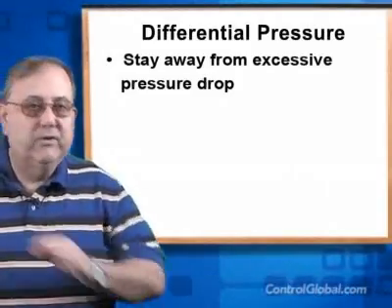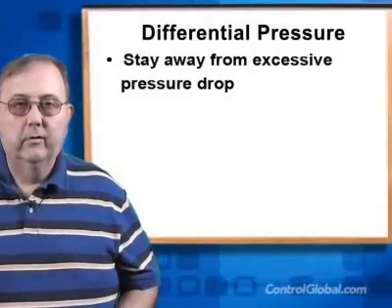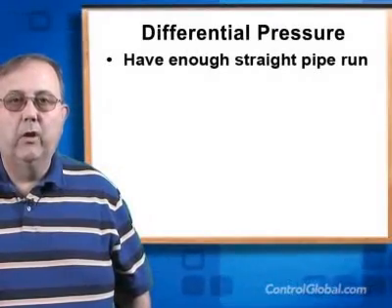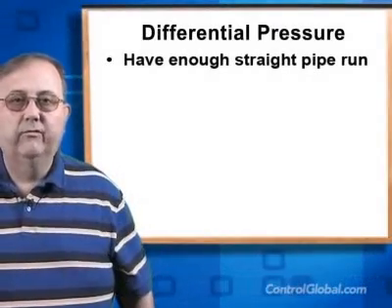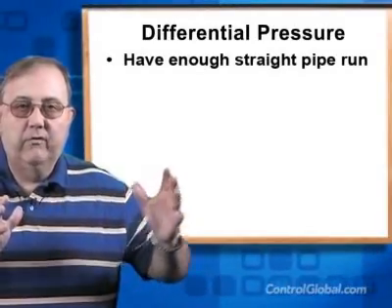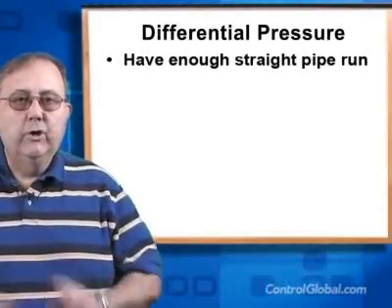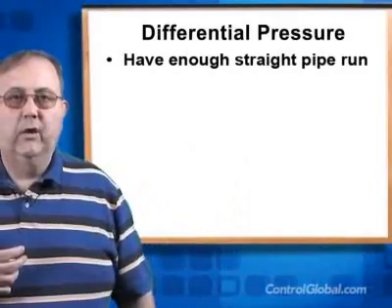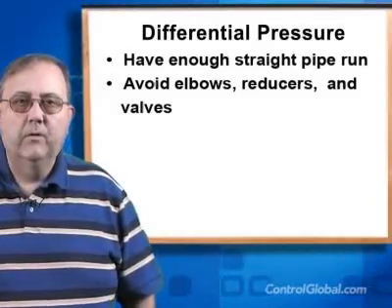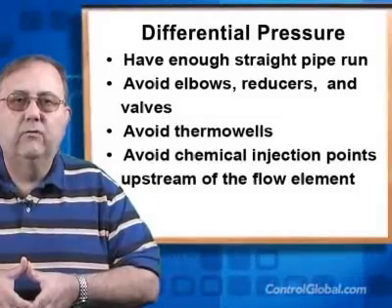Make sure that the pressure drop is not excessive at maximum flow rates to keep abrasion down. Very importantly, make sure you have enough straight run upstream and downstream of the flow element to ensure accurate flow readings. The old rule of thumb of 10 diameters upstream and 5 diameters downstream doesn't always work. In the case of spiraling flows, for example, you need 100 diameters upstream if you can get them. Elbows, reducers, and valves increase the amount of run you need. Thermo wells and chemical injection points can also seriously affect the accuracy of the measurement.